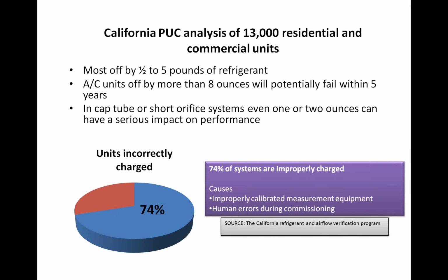California PUC did an analysis of 13,000 residential and commercial units. They found most were off half a pound to 5 pounds of refrigerant. AC units that were off by more than 8 ounces would potentially fail within 5 years. So compressor failure, contactor failure, they could short cycle due to a high pressure switch or a low pressure switch, but they have some kind of a failure within 5 years. In the cap tube systems or short orifice systems, even an ounce or 2 of refrigerant would have a serious impact on performance, and they found almost exactly the same thing: 74% of units were incorrectly charged. The causes of this were improperly calibrated measurement equipment and human errors during commissioning.